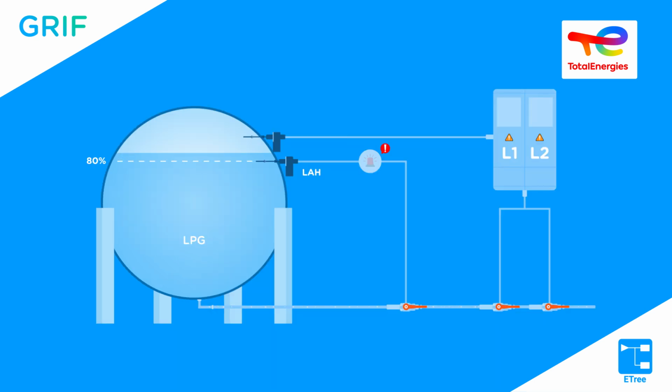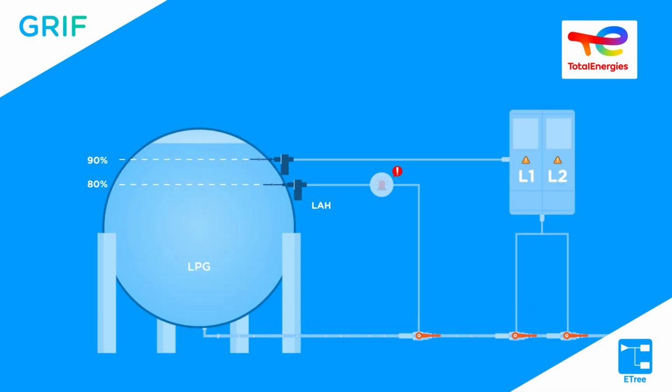If the first barrier is down and the gas level is upper than 90%, a safety instrument loop is implemented. The safety system is one level sensor, LSHH, connected to the control unit, and the final action is to close one of the two SDV. If both preventive layers fail, a 65 mm leak appears on the LPG storage sphere.